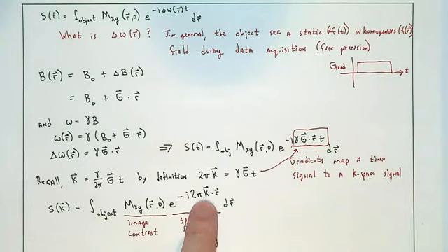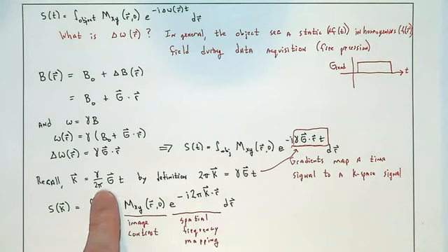Well, this k vector that we have here is dictated by the applied gradients, right? The last substitution that we just made explicitly wrote it out: the gradient vector that we have applied will define the k vector. And the stronger the gradients and the longer they are applied for, the bigger your k vector. You'll see in just a second, or later this afternoon, how these gradients move us around through k-space. The gradients themselves have history. We turn them on, we turn them off. They have positive signs, they have negative signs. And that will directly dictate where we are in k-space. If you look at the units of this, you'll end up with units of spatial frequency, so cycles per distance, if you will.